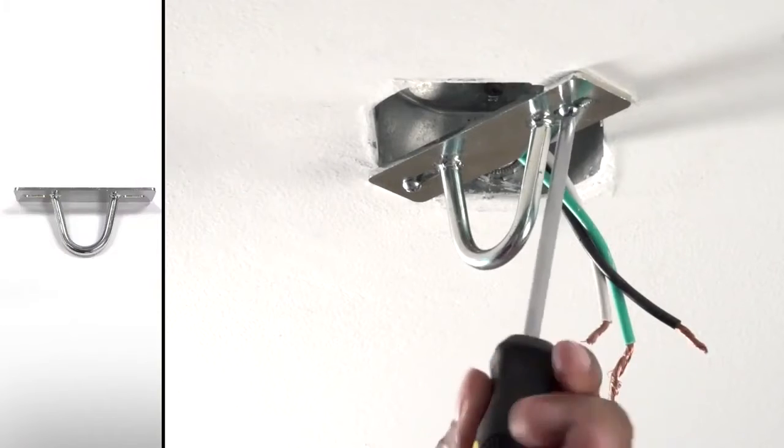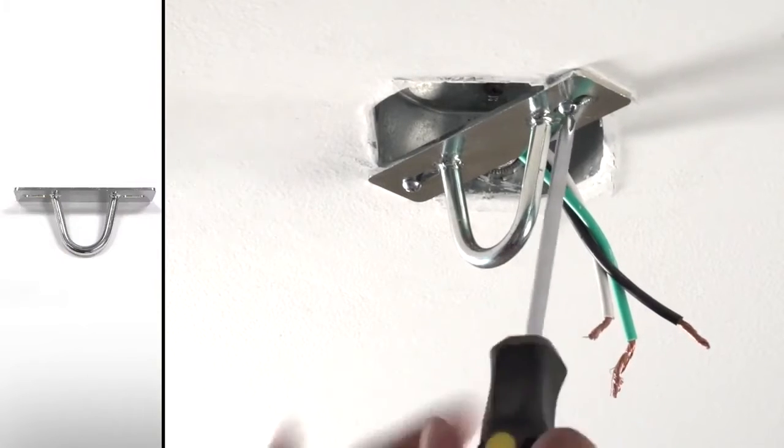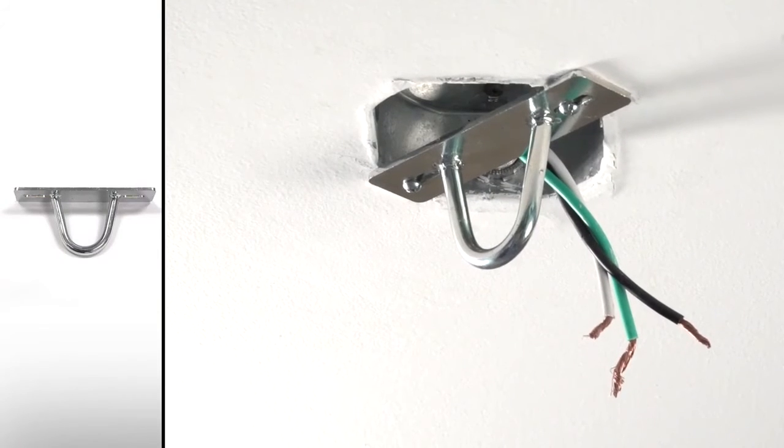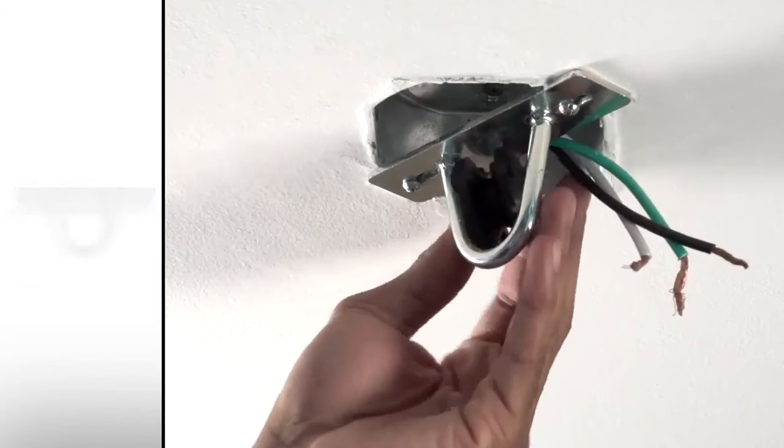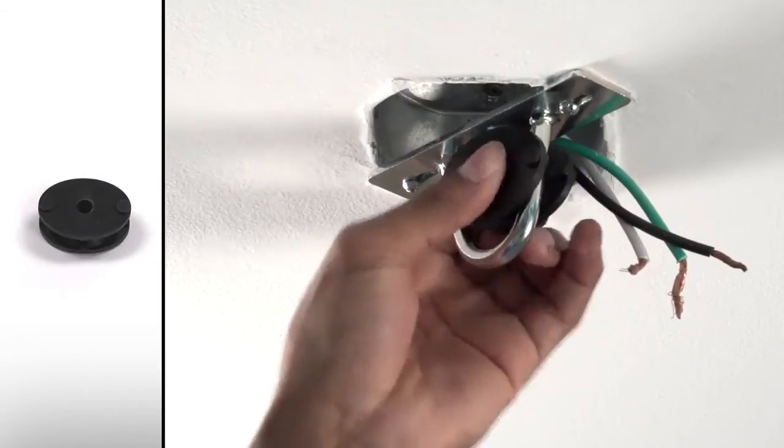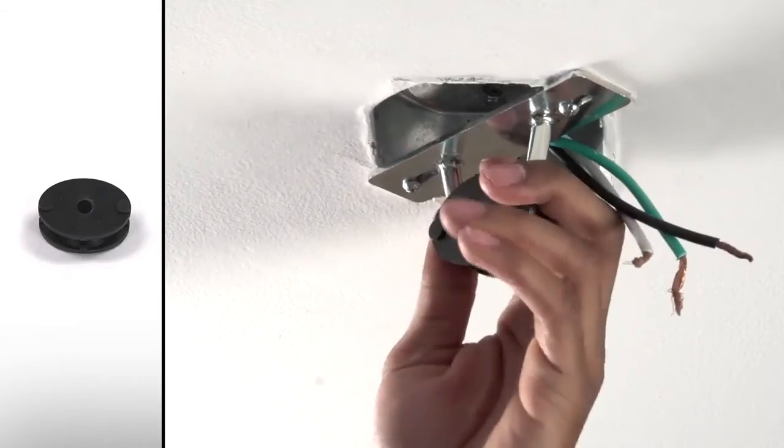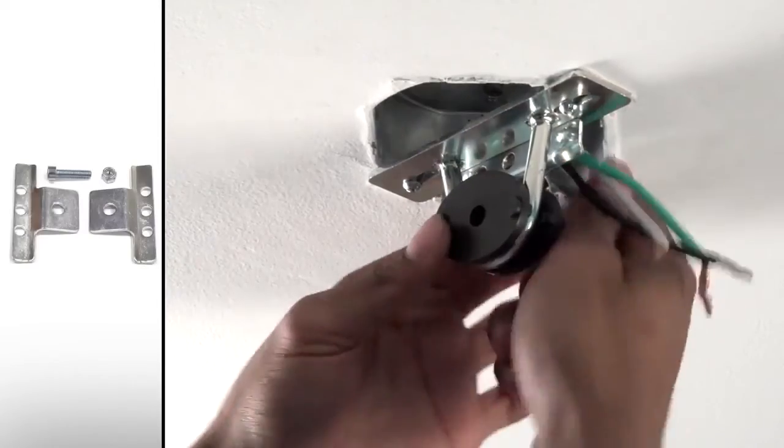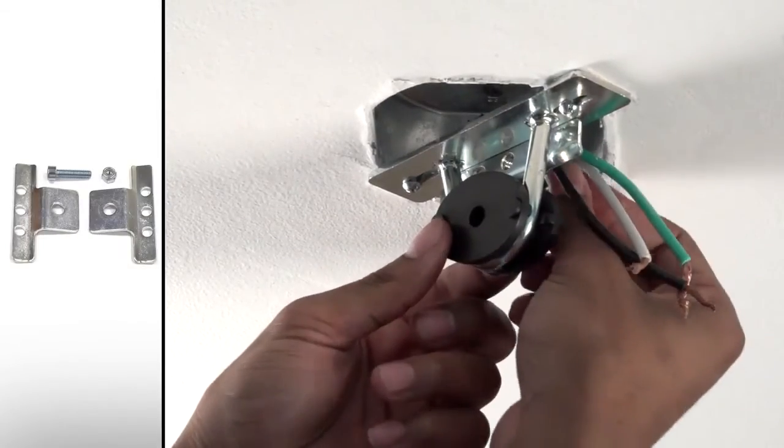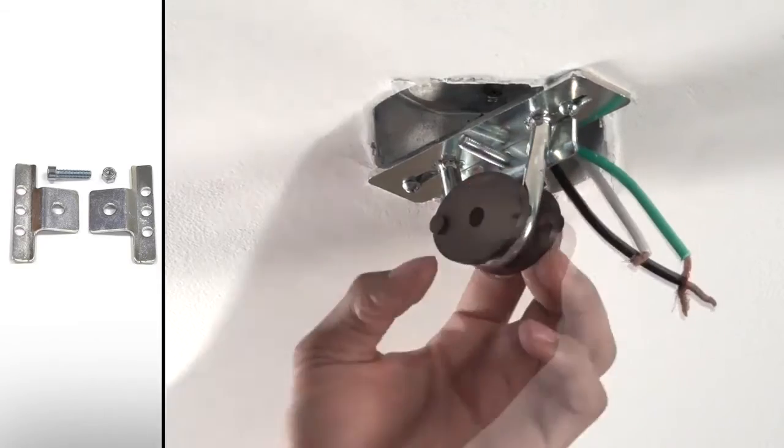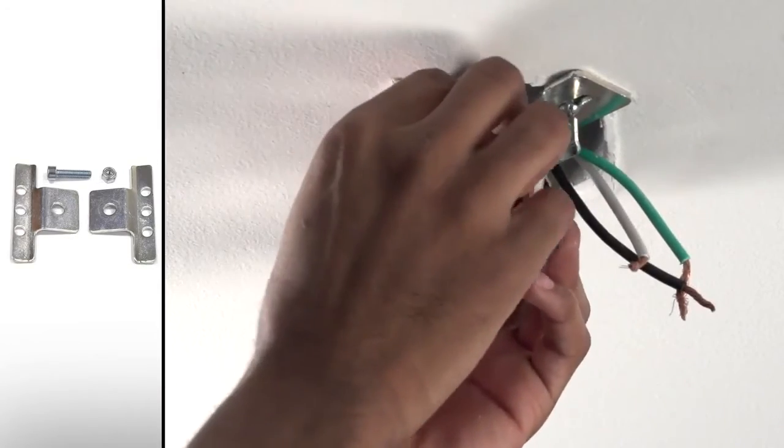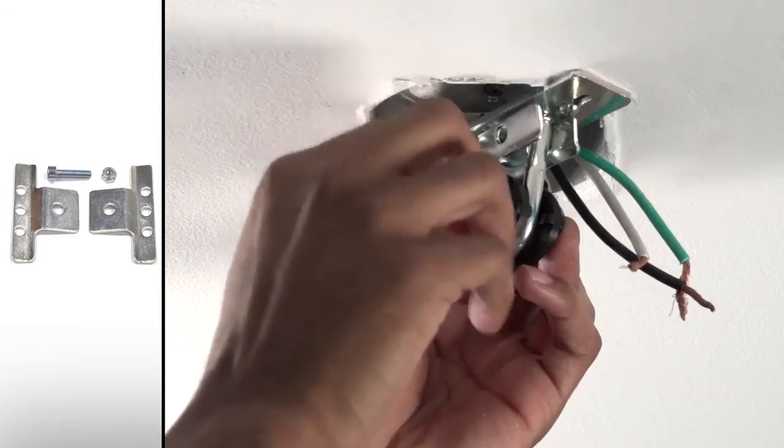Secure the mounting bracket to the outlet box using the hardware supplied with the outlet box. Secure the rubber bushing in the eye of the mounting bracket. Loosely install the mounting brace brackets with the provided hardware. The bolt should be inserted in the middle bolt hole on the brackets. Do not fully tighten the hardware.